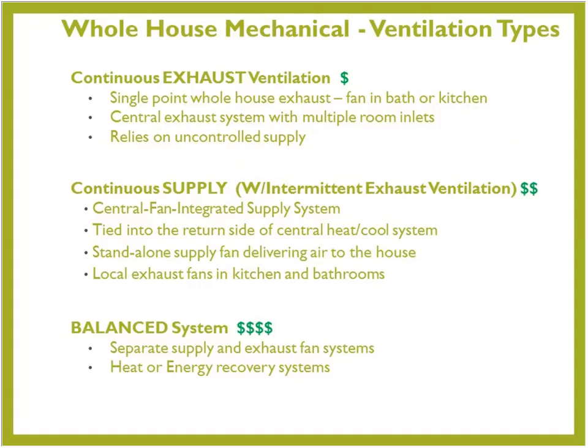Exhaust ventilation is just what you guys have been doing, what most people have been doing for the past 20 years. It's just bathroom fans or kitchen range hoods, taking air from the pollution source and exhausting it to the outside of the building, or in some cases to the attic, which we don't want, pumping moisture up there either. We want to make sure it gets completely out of the building. So nailing the duct up to your vent on the roof, or throwing it into the soffit and expecting it to make its way to the exterior, is not going to work. But that's what we've been doing in a lot of cases over the past 20 years, the exhaust-only approach.